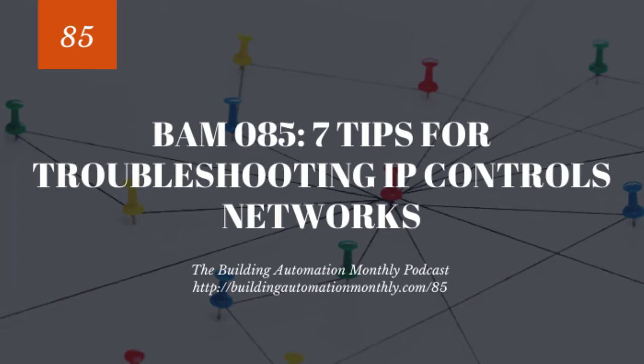But at least with BACnet MSTP and with Modbus, you could use registers or MAC addresses that were unique to that network segment but weren't unique overall. But when you start to get to IP addressing, now you're starting to deal with things where you have to have unique IP addresses, at least in the private subnet class that you're using.